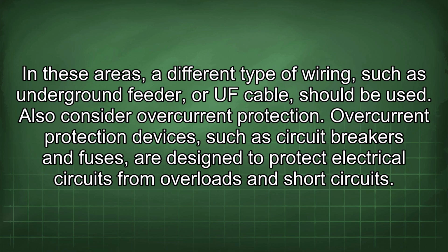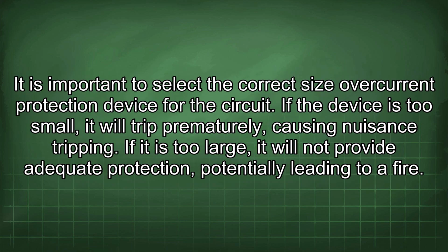Also consider overcurrent protection. Overcurrent protection devices, such as circuit breakers and fuses, are designed to protect electrical circuits from overloads and short circuits. It is important to select the correct size overcurrent protection device for the circuit. If the device is too small, it will trip prematurely, causing nuisance tripping. If it is too large, it will not provide adequate protection, potentially leading to a fire.